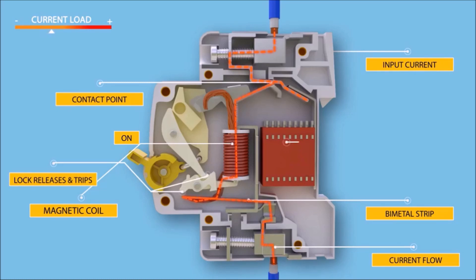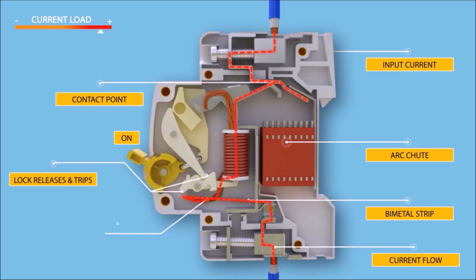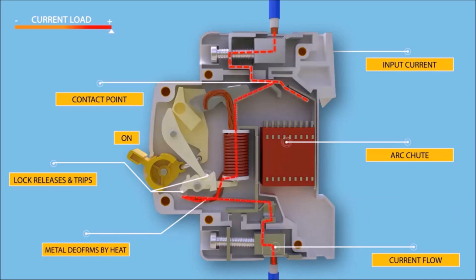The visual indication of this trip can be observed by the automatic movement of the operator to the off position. During tripping operations, an arc is formed when the contacts start separating. This arc is then forced into the arc chute plates, where it is divided into a series of arcs, and at the same time energy is extracted and it cools.